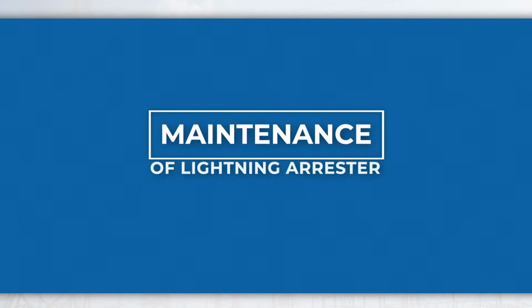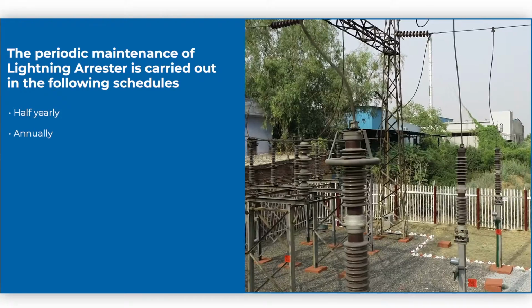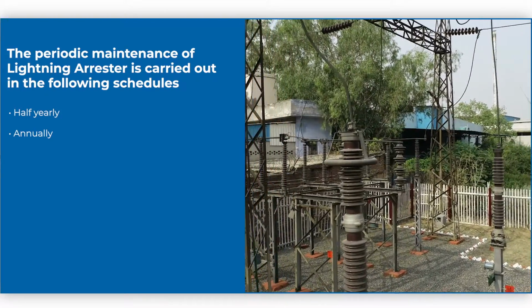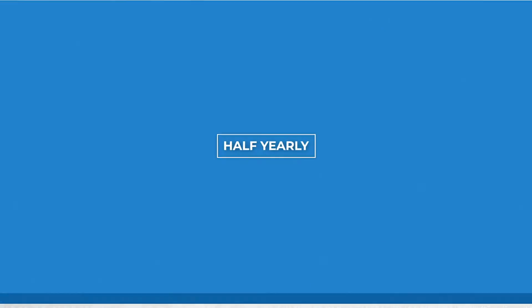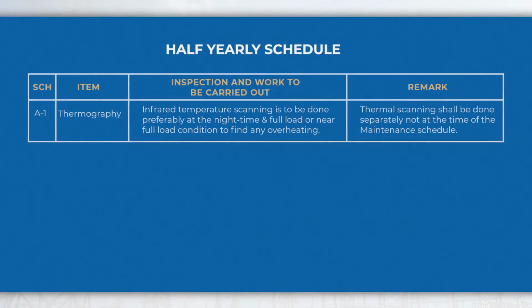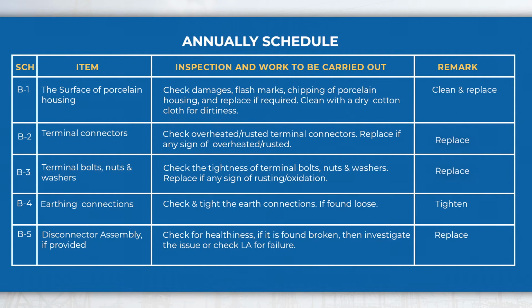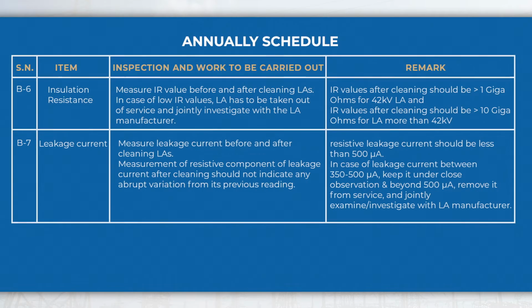Maintenance of lightning arrestor. The periodic maintenance of lightning arrestor is carried out in the following schedules: half-yearly and annually. Half-yearly schedule. In the half-yearly schedule, do the thermal scanning. Annual schedule. In the annual schedule, perform activities like checking the insulators, terminal connectors, earthing connections, checking the healthiness of disconnector assembly and measuring IR value and leakage current, checking the physical condition and functioning of indicators of the surge monitor, etc., in addition to half-yearly schedule activities.